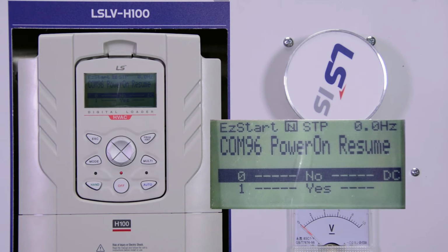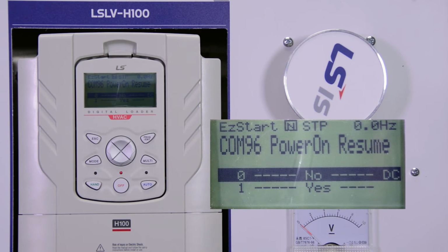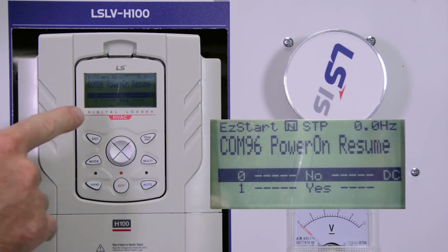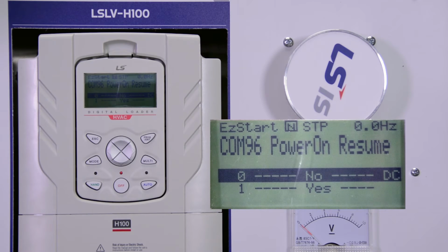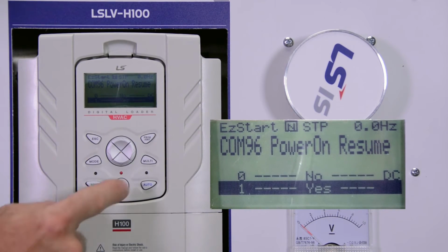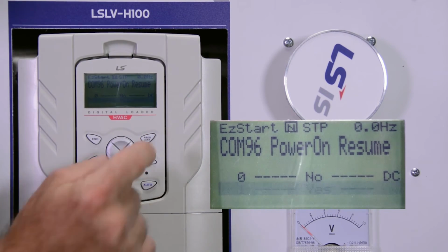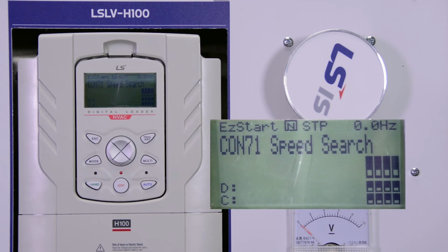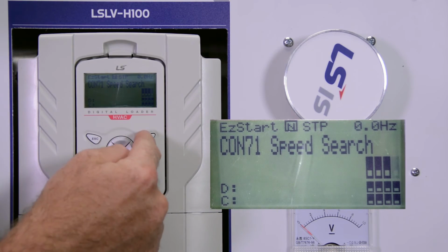If for some reason you would lose power to the drive in a remote location and you want the drive to automatically restart, you can change the next question, power on resume. You change it to yes and select enter. That power on resume only works if there is a digital input telling the drive to start. If you want to do a speed search, you can change some bits there. In this case, we don't need to do anything.